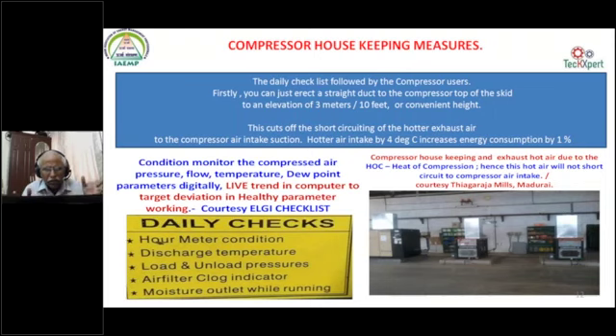Then the compressors are all installed, but the hot air that is exhausted from the top of the compressor is again sucked back into the compressor. Why don't we have the provision to extend a duct outside of the compressor house? At least let us have a 2 meter or 3 meter duct on top of the compressor, so the hot air is moved away and the compressor always gets cool, dry air to compress. These are all the areas. Every 4 degrees rise means 1%. Say around 5% possibility of savings is there in the compressor house. Let us do it.